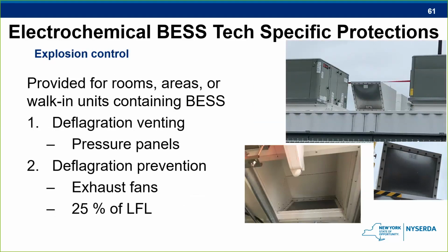So as I touched on a little bit earlier, some system types, like lithium-ion, have the potential to release explosive gases when malfunctioning, overheating, etc. And explosion control can be handled in two ways, rather: deflagration venting and deflagration prevention. So most lithium-ion systems will have deflagration venting panels that will manage the overpressure blast wave that's produced in an explosion. That blast wave will be sent through the venting panels and should maintain the integrity of the container. The panel's venting direction should be directed to an area that won't interfere with the fire department operations or otherwise hurt someone. And as discussed earlier, while not required for normal operations, exhaust ventilation can be used for lithium-ion systems as part of explosion prevention.